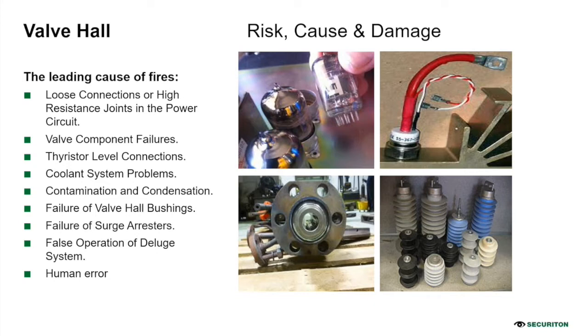Then we have valve component failures, the heart of the HVDC link. Any HVDC link, any HVDC room, has the valve. In HVDC systems, faults on the rectifier side or inverter side have a major effect on system stability. The various types of faults considered in the HVDC system are basically due to the malfunction of valves and controllers as well. Misfire and short circuit across the inverter station.